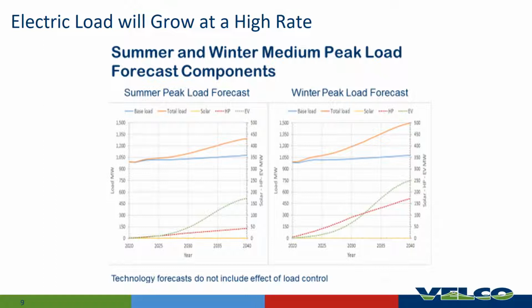You have to. You're not going to have distribution capacity to do it. You can't fast charge at 9 kW, 12 kW, 15 kW in somebody's garage and try to do that on the existing distribution system, so you have to manage them. If you look at this, the base load, which is running around 1,000 megawatts, goes up 400 megawatts just in the summertime, and that's due to car charging and also heat pumps running as air conditioners.